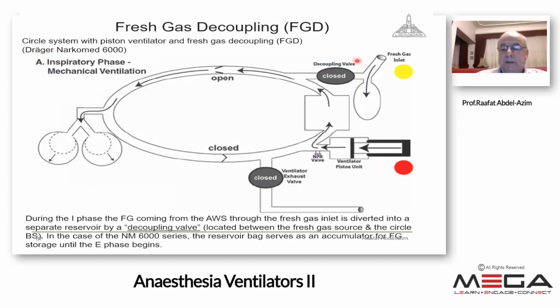So the first thing this manufacturer has achieved is removing the bellows and replacing it with a piston. The second thing is applying what is called fresh gas decoupling. This fresh gas decoupling valve is inserted between the reservoir and what is coming from the fresh gas flow. During ventilation with traditional ascending bellows ventilators, during inspiration the fresh gas flow will go directly into the inspiratory limb without any obstacle. But here, with fresh gas decoupling, there is what we call a decoupling valve. The decoupling valve will be closed during inspiration.